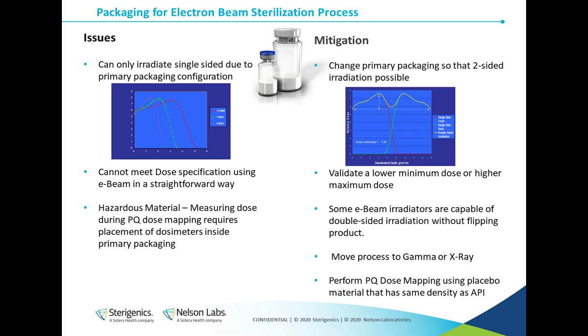One thing we might do is change the primary packaging in some way so that we could irradiate the product from both sides. We could try to validate a minimum dose that's lower or a higher maximum dose, but that might not be practical in this case. We could use an E-beam irradiator that irradiates the materials from both sides without the need for flipping the box, as there are some designs that allow for this. Or we could ultimately decide to use gamma or X-ray for this process.